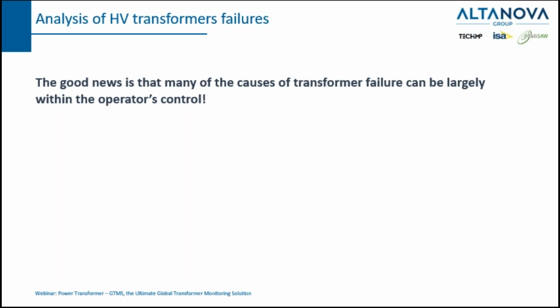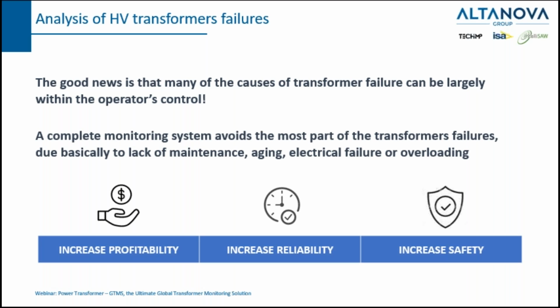So the good news for all of us is that many of the causes of transformer failure can be largely within the operator's control. A complete monitoring system avoids most transformer failures, due basically to lack of maintenance, but also aging, electrical failure, or overloading. And last but not least, a complete monitoring system also helps transformer operators increase, as you can see here, the profitability, the reliability, and the safety, not only of the transformer, but of the entire substation or installation.